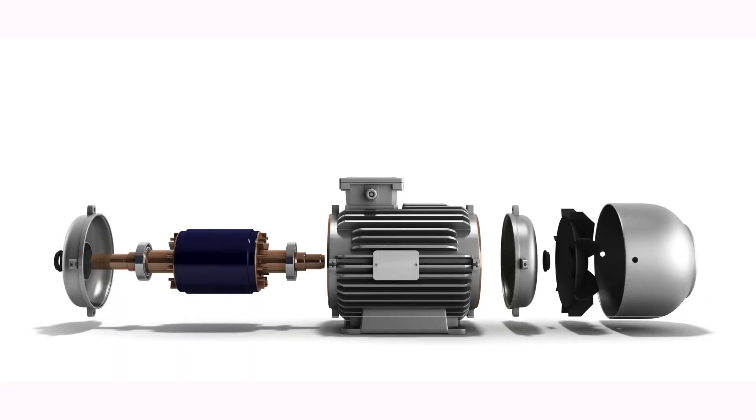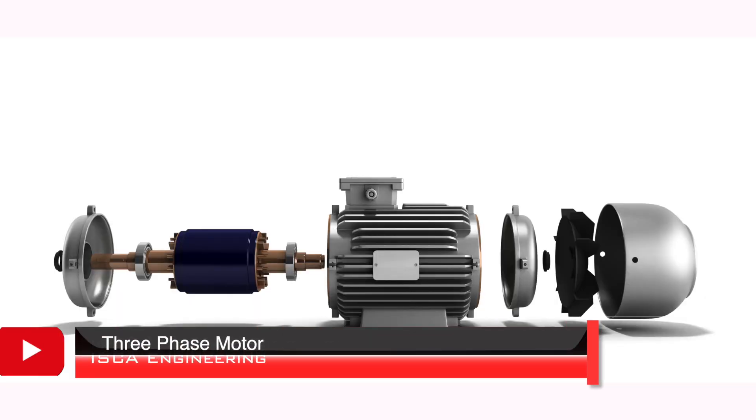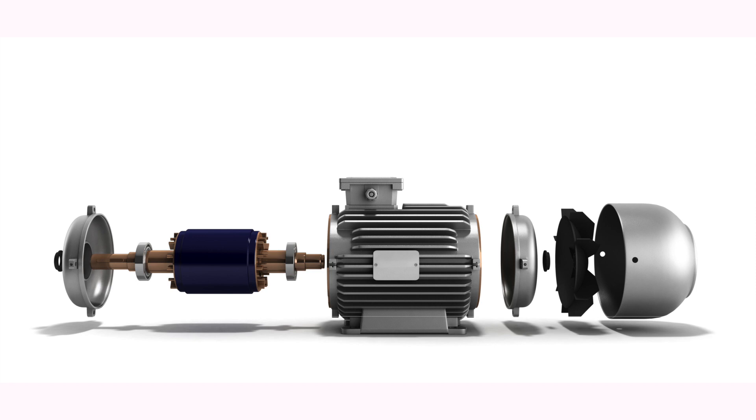The most commonly used AC motor in industrial and commercial applications is of course the three-phase. When needing large amounts of horsepower, it's best to use a three-phase motor instead of a single-phase motor. The thing is, the single-phase large horsepower motors are very inefficient compared to a three-phase motor. In addition, single-phase motors are not self-starting on their run windings, as are the three-phase motors.